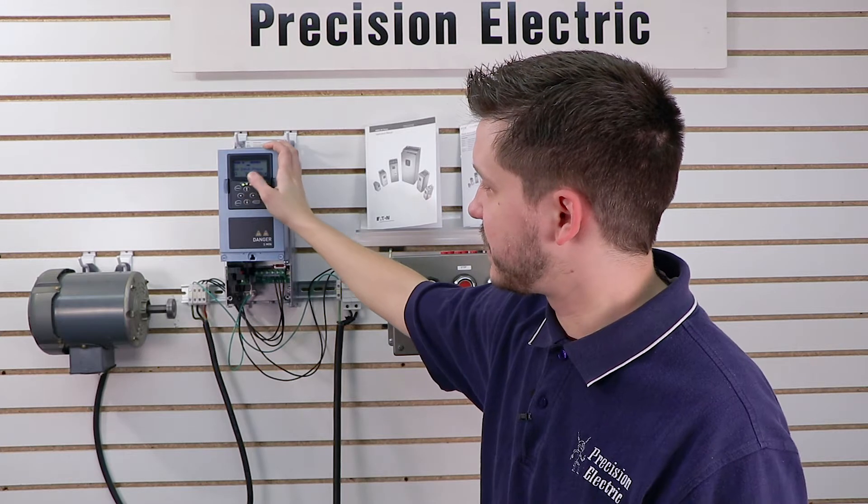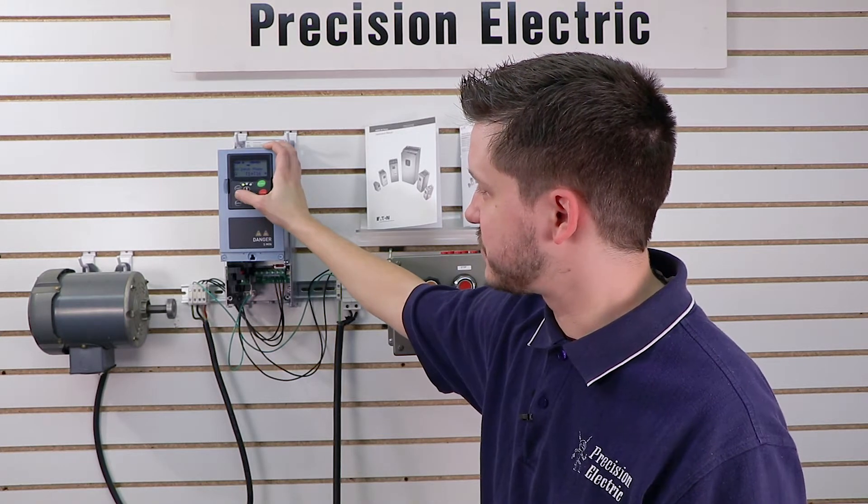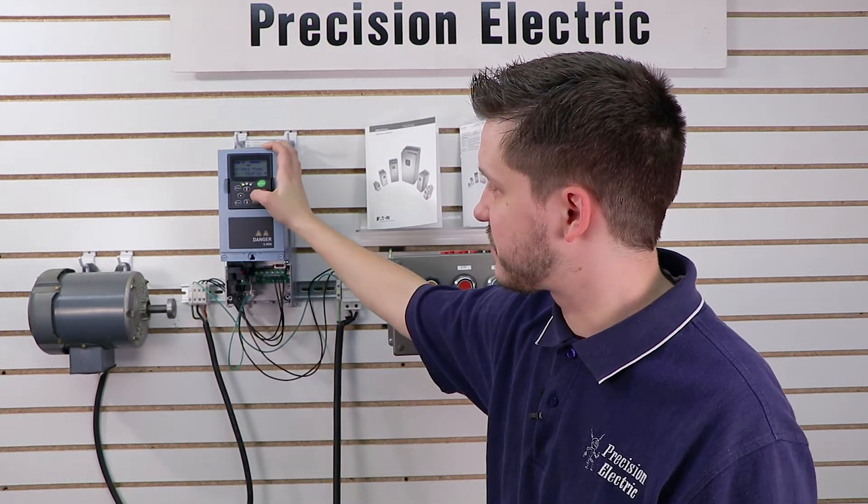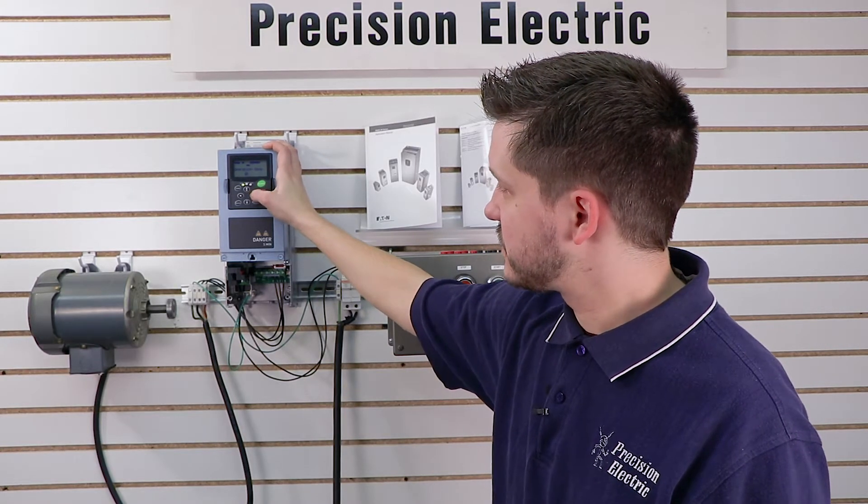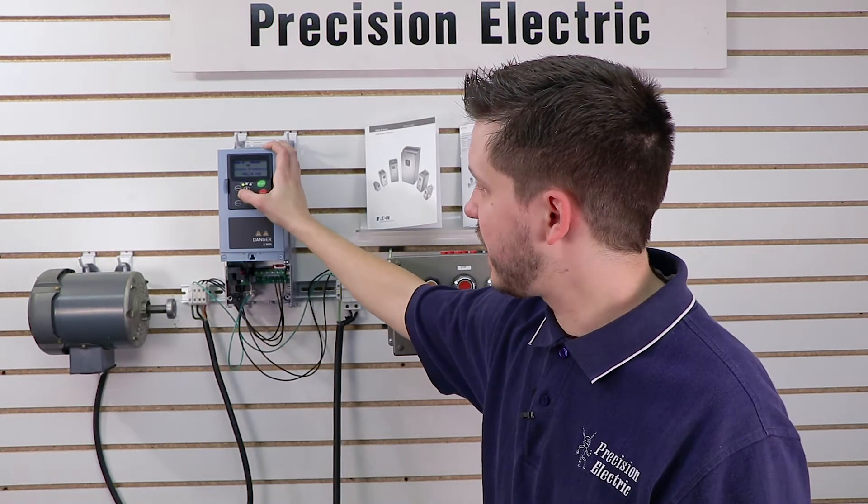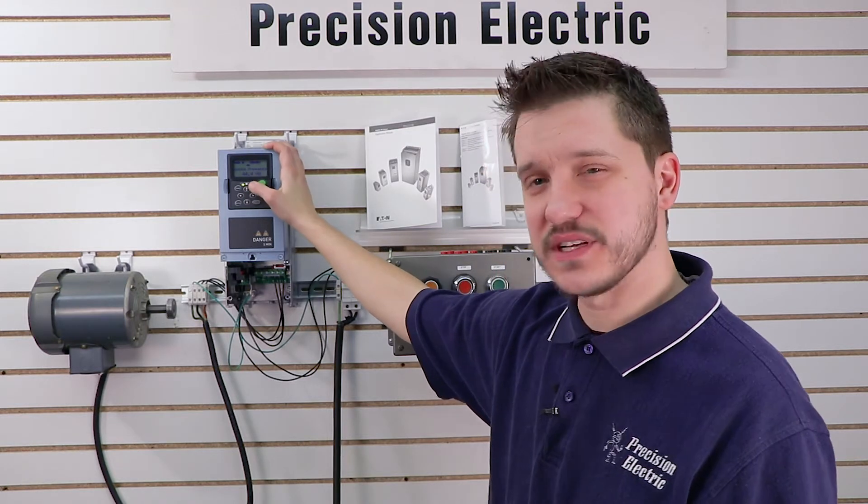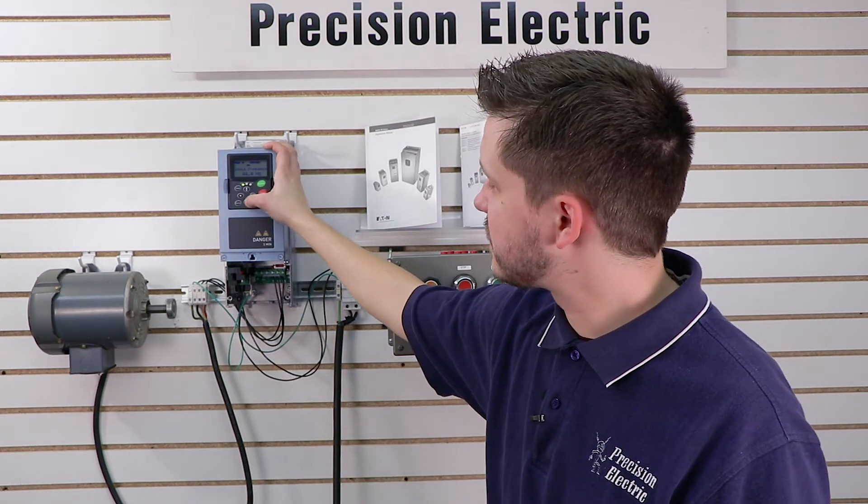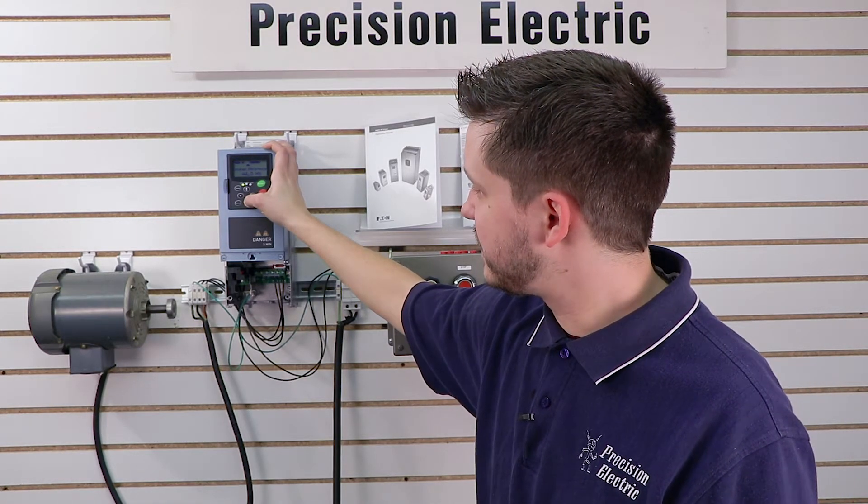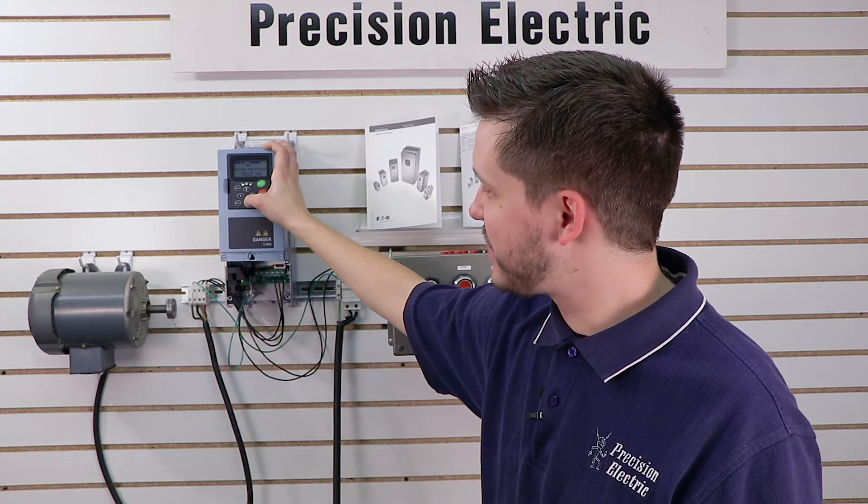But right now I'm not in the right menu. I actually have to use these left and right arrow keys first to get to my output frequency. Right now it's set to 44.4 hertz. So if I press the down key, it'll switch to keypad reference. And you'll notice the numbers start to go down.